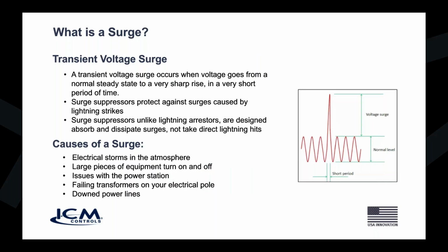So, it's a direct lightning strike. Pretty much, you got to have a different type of a device, something like a lightning arrestor or something like that. Surge suppression devices do not cover that. These are to suppress the surge, clamp the voltage at a certain level, and then just dissipate the rest of the surge as heat, but not take a direct lightning hit.